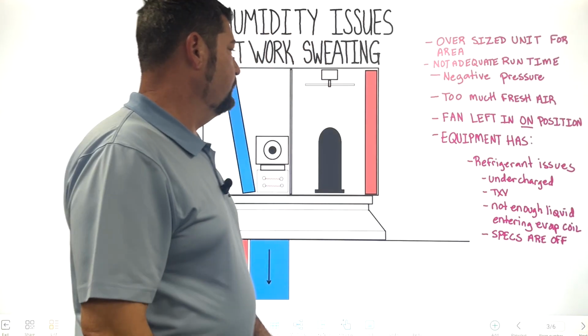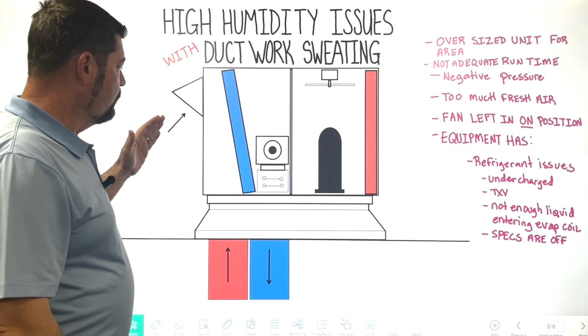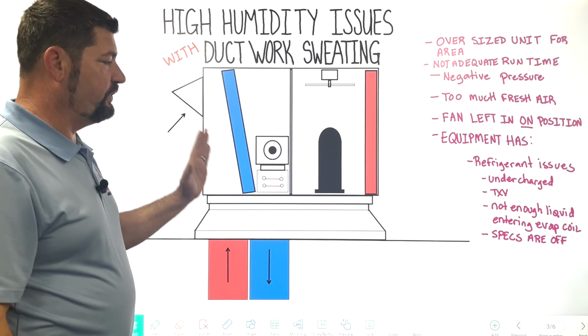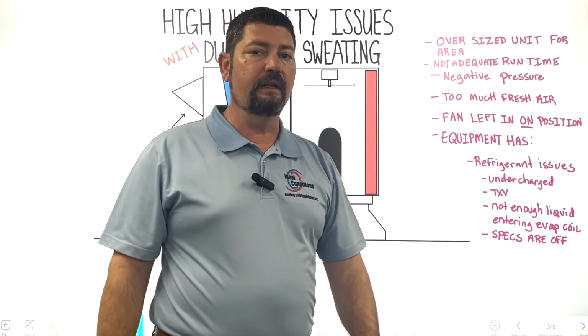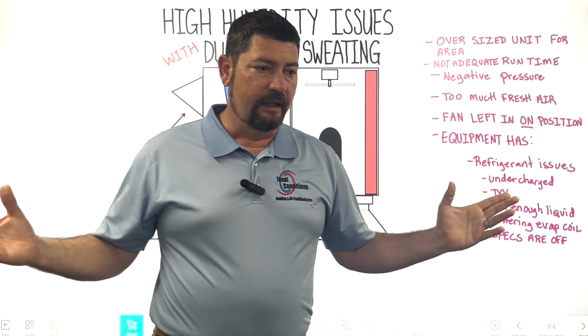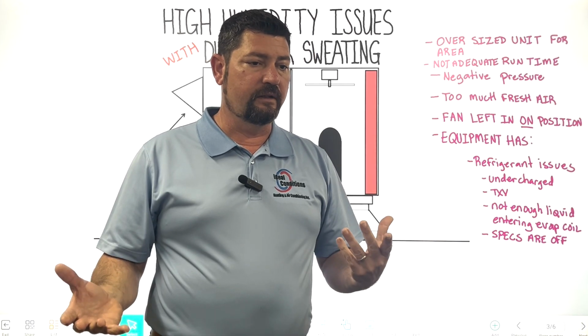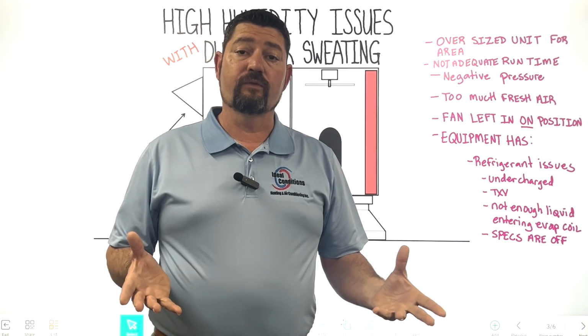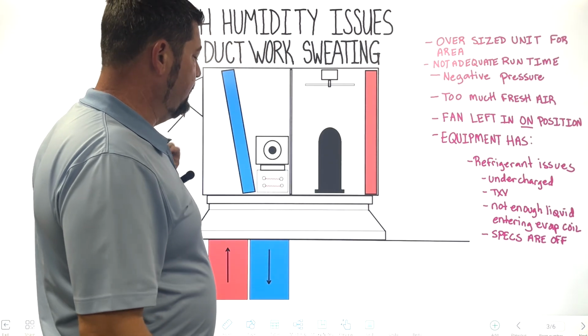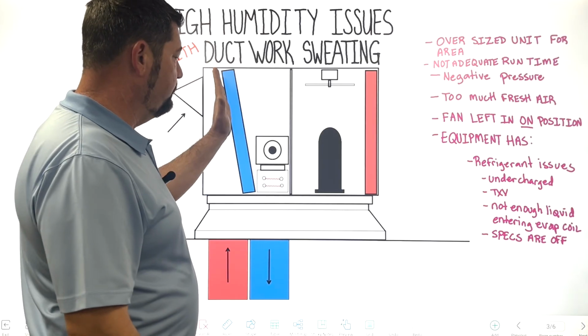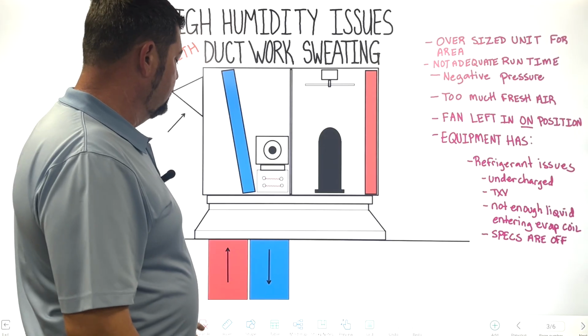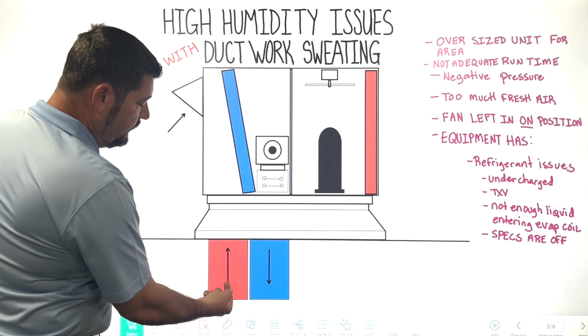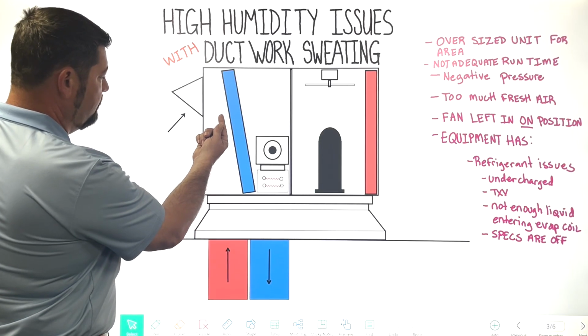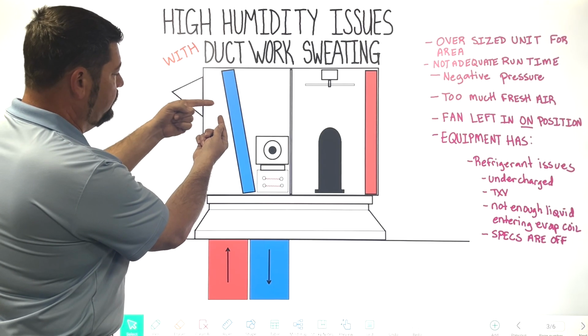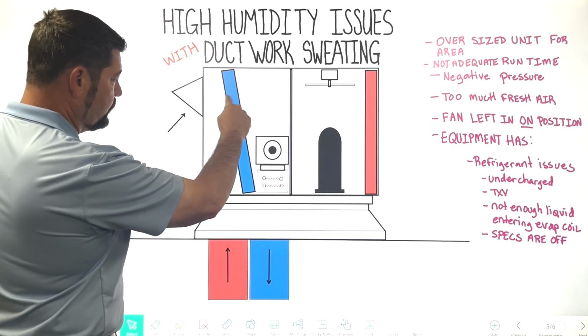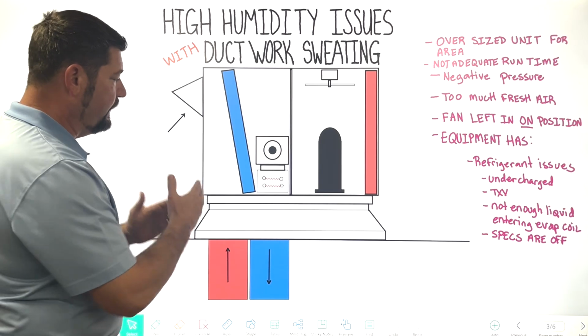Having too much fresh air is also not good. So if you have more outside air coming in than this coil can actually dehumidify, then you're going to raise the humidity in the building. So let's just say it's raining, and at the end of the day, it's not that much of a heat load, and the unit does not have to run that much, and more humidity is being added to the structure through the fresh air than is being removed by this cold coil. Then we may be coming in at, say, 55% relative humidity, but then maybe we're adding an additional 20% humidity, so that's 70% relative humidity going across the coil that's not condensing at the same rate as the moisture that is taken in.